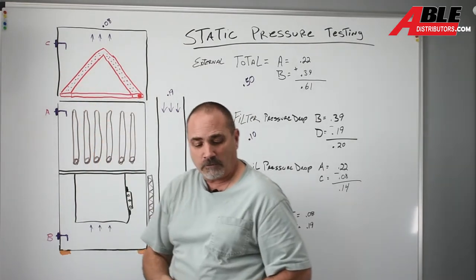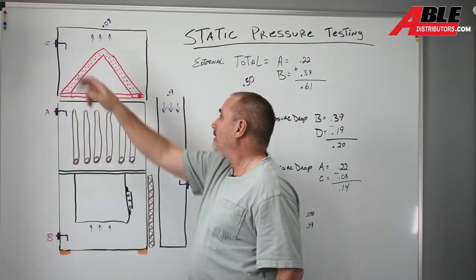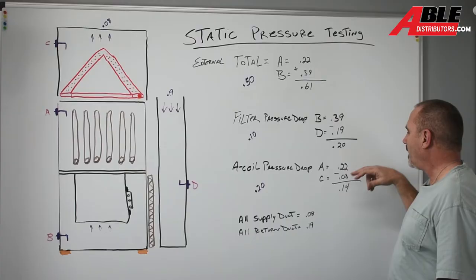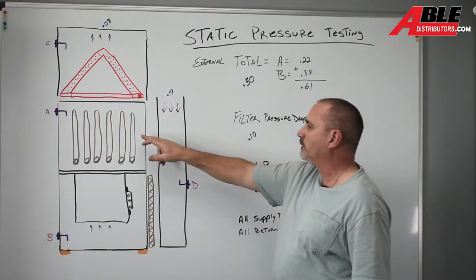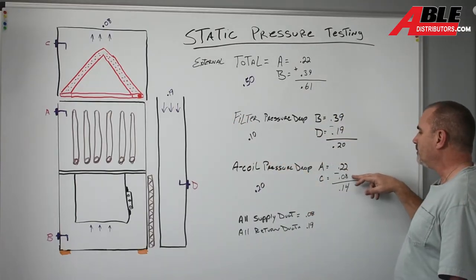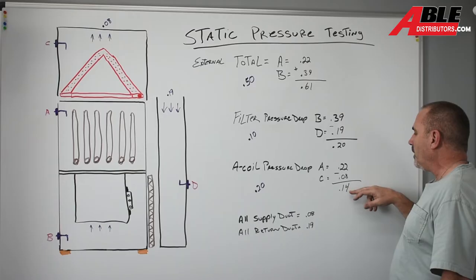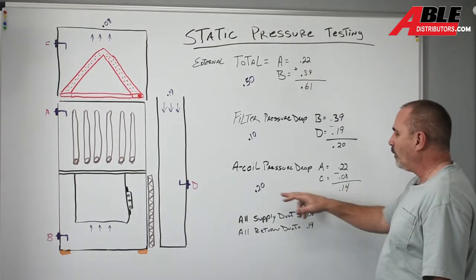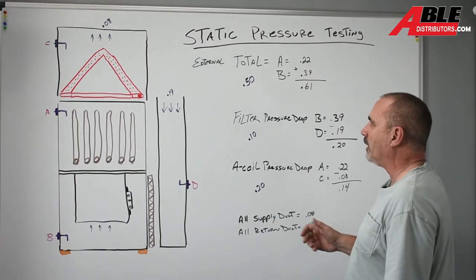We're going to take that minus that. So we've got 22 still here, and then on the top of the A coil is 0.08. So that means the A coil drop is 0.14. We allow for 0.20, so we're good there.